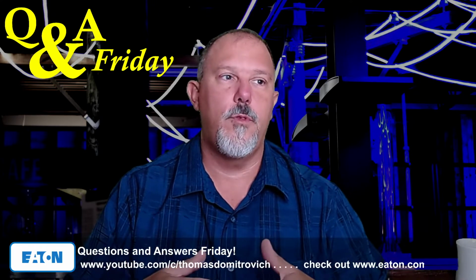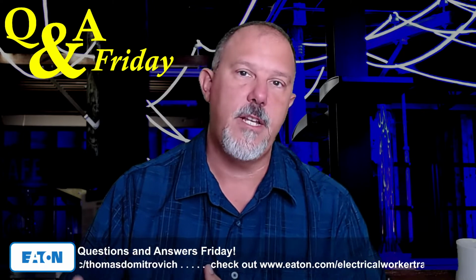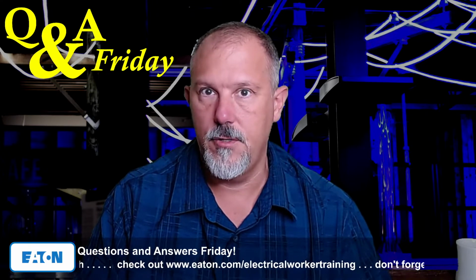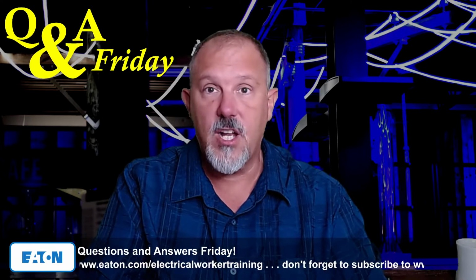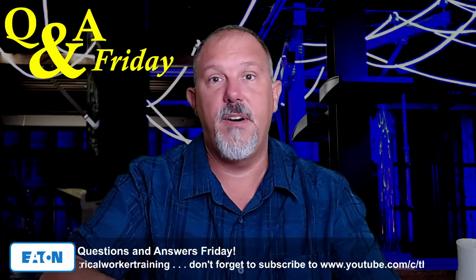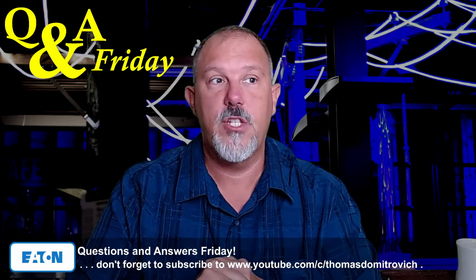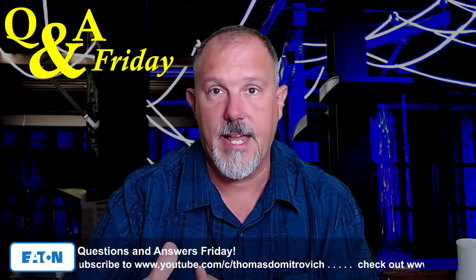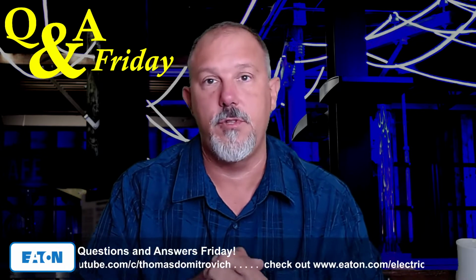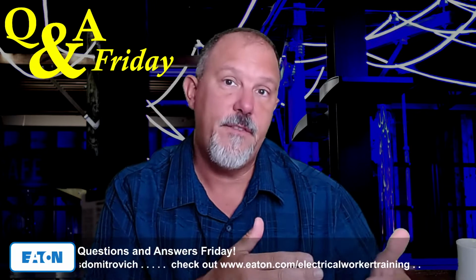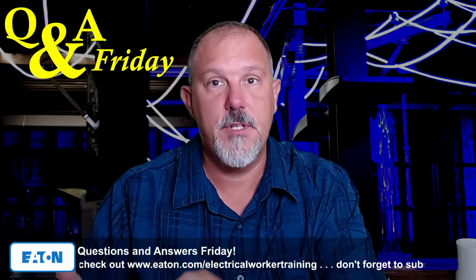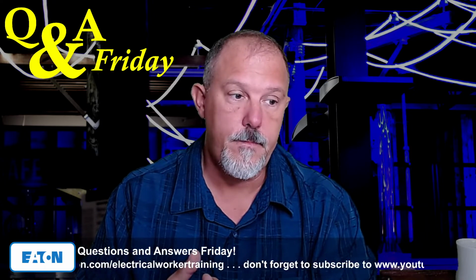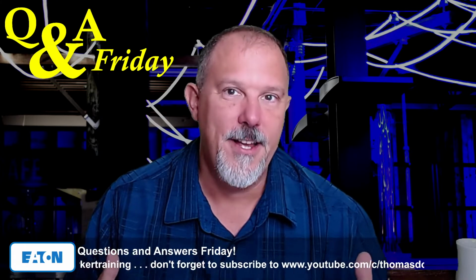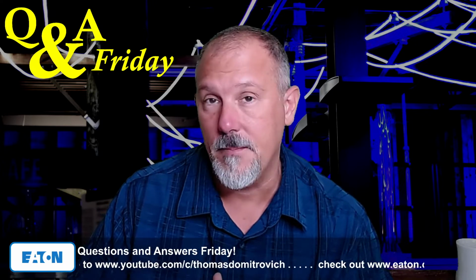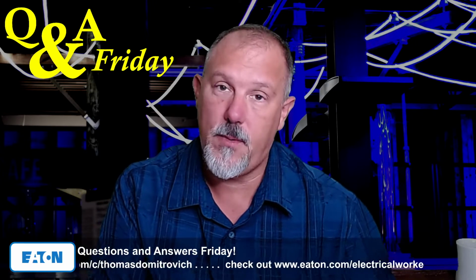The more complicated the assembly, the more of a challenge it is for the electrical worker to understand the hazards, right? We teach people in 70E, when we talk about safe work practices, what shock is. We teach that above 50 volts we talk about the shock risk analysis, understanding and recognizing shock hazards, and how to test for absence of voltage. But if that individual doesn't understand everything that needs to be tested for absence of voltage in a specific piece of equipment, you may be really good at testing for absence of voltage, but you didn't test everything you needed to test, and there still might be energized components within that assembly because you're not as familiar with the equipment and all that it brings to the table.